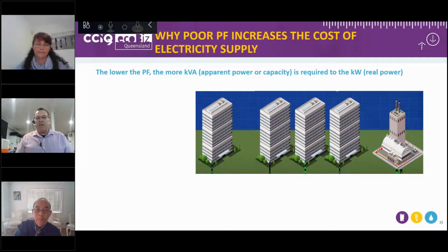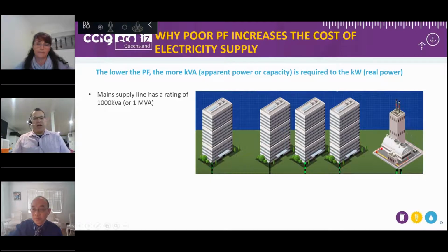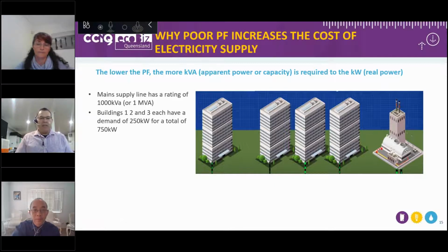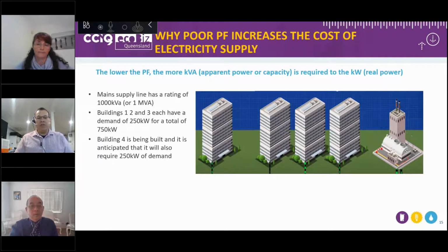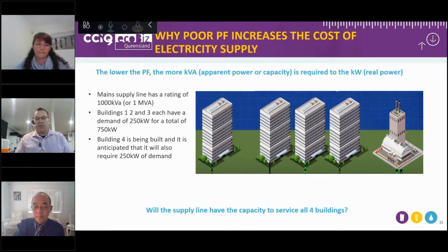Okay, so why does poor power factor increase the cost of electricity supply? I'm going to try and run through a little example. Here we've got, from the power station on the right-hand side, a need to supply 4 buildings with power. There is a 1 MVA line that can supply these 4 buildings. Buildings 1, 2, and 3 each have a peak demand of 250 kilowatts, for a total of 750 kilowatts. Building 4 is being built, and it is anticipated that it will also require 250 kilowatts of demand. Will the supply line of 1 MVA have enough capacity to service all 4 buildings?